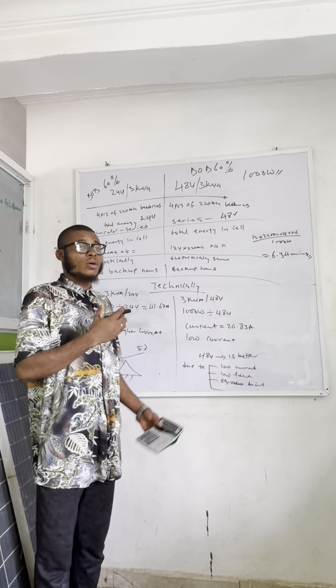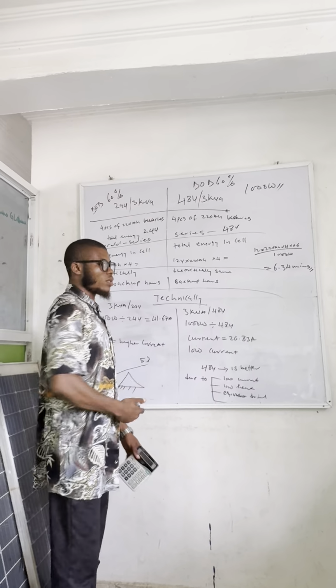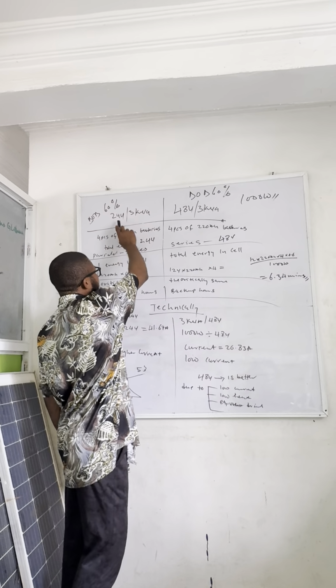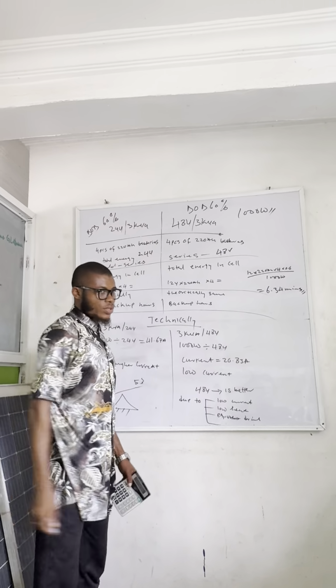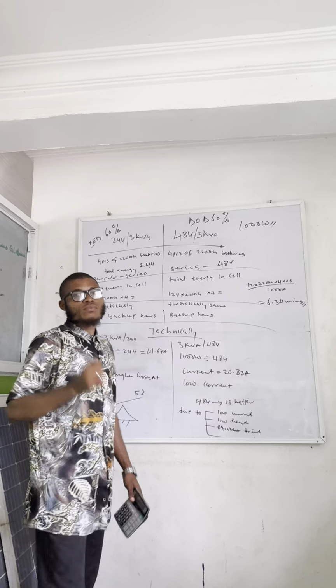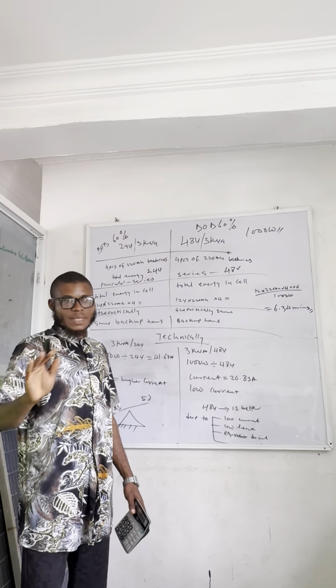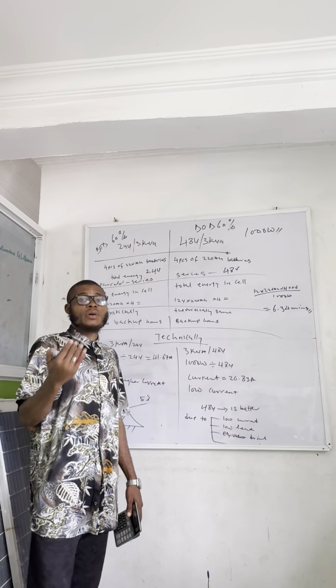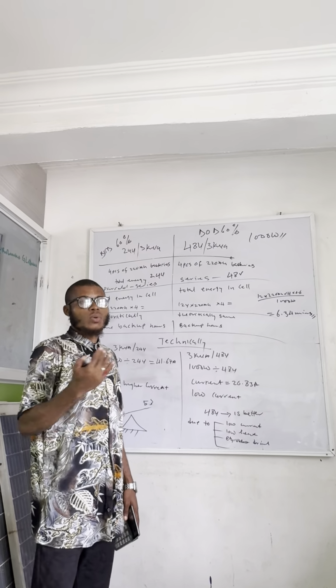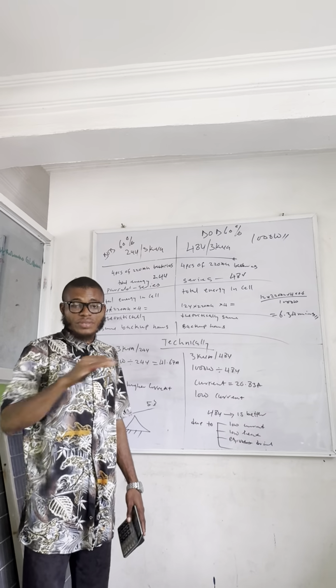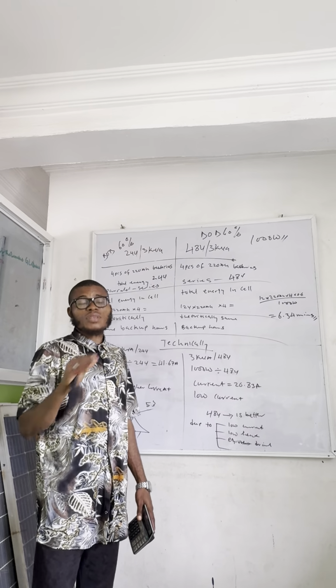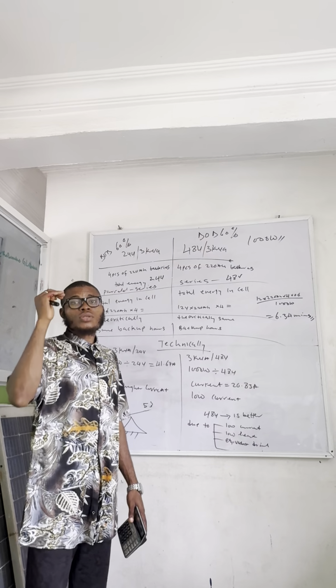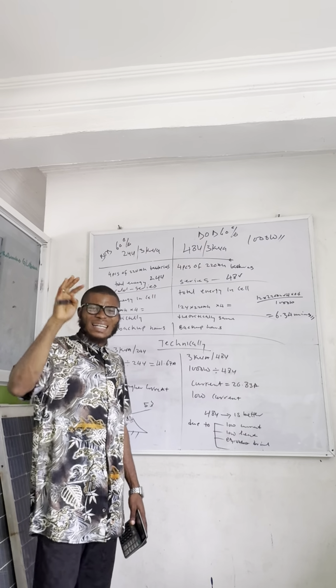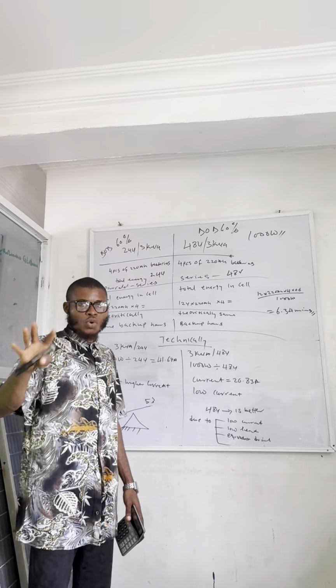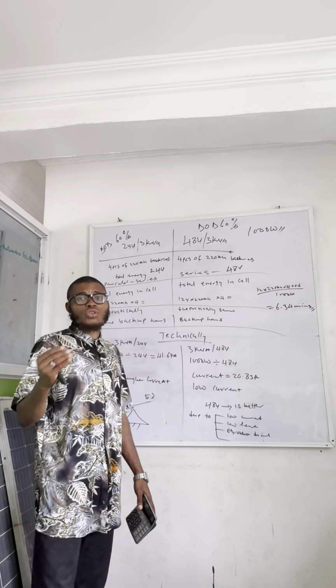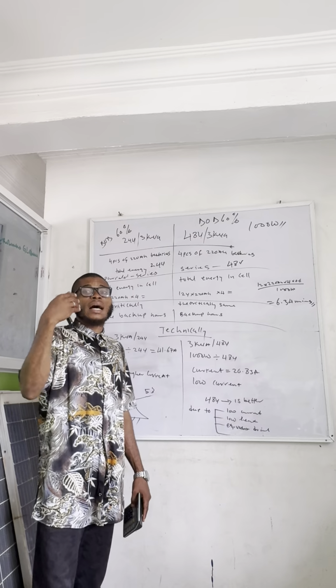Alright, somebody tagged me under a comment section, that solar analyst. If I have a 3 kVA 24 volt and a 3 kVA 48 volt with 4 batteries each, which one is going to back up better? And I asked him under the comment section that before I could answer you correctly, I need to know: are those batteries the same? The inverter, is it the same inverter from the same factory, the same company? Do they have the same power factor, and are they also running the same amount of load? So these are the critical questions I wanted him to provide me an answer to.